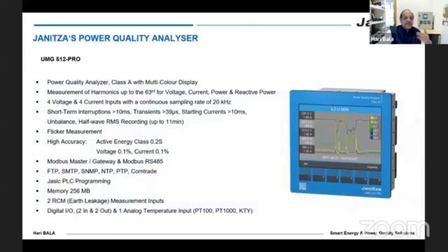Modbus, it can have a Modbus gateway. You can have a Profinet or even BACnet, for example, if you wanted to use it with your building management systems. And it also has an Ethernet port, which complies to FTP, SMTP, SNMP, and COM-trade formats. Memory is around 256 MB. Our usual factory memory recording is allowing almost around 6 months of data inside the meter, a standard configuration.